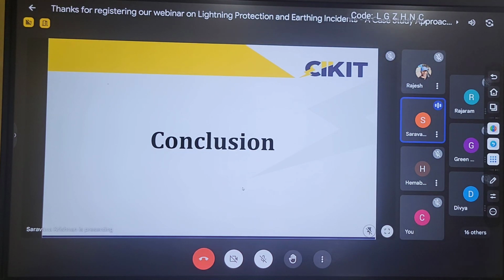Depending upon the site conditions, we can select either the rolling sphere method, the protection angle method, or the mesh method. But because of rooftop solar installations, many people are nowadays not going for the mesh method. The two commonly used methods are the protection angle method and the rolling sphere method. Among these two, rolling sphere is more preferred because of its advantages. The standard does not mention that I have to go for only 1 meter or 2 meter height of air terminals. Based upon our requirements, I can increase the height and perform the calculations accordingly.